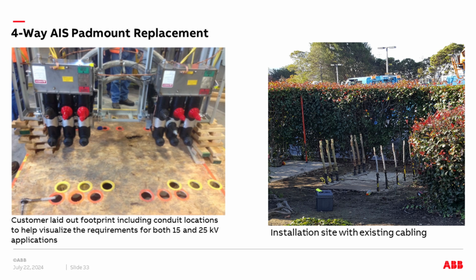And then we show here that in order to figure out how to make the spacing work, the utility actually mocked up in their shop floor plans on this wood platform where the cables are and the conduit openings, in order to make sure the gear was going to fit. And then you get to the job site picture on the right, where the old gear has been removed, and you can see these cables sticking up out of the pad. They really can't be moved. So it's not an open pit of any kind. It's just fixed concrete locations, and then the cables can be cut and re-terminated with shielded elbows.